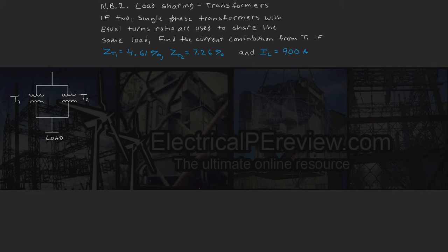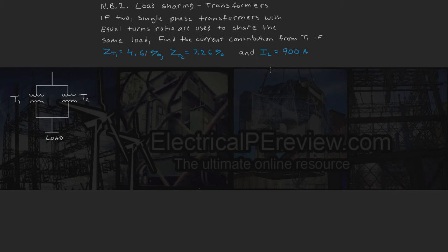If two single-phase transformers with equal turns ratio are used to share the same load, find the current contribution from transformer 1. The impedance of transformer 1 is 4.61%, the impedance of transformer 2 is 7.26%, and the load current is 900 amps.